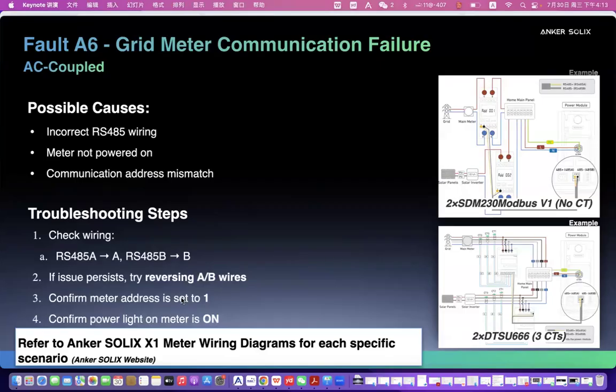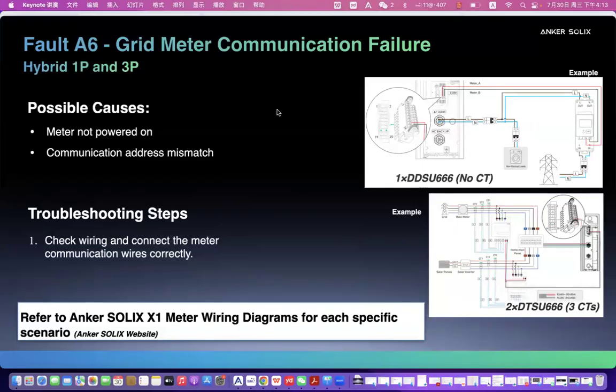And another thing to focus on is we also have this SDM230 Modbus V1 meter. This meter needs the address set, and other meters do not need the address set. So if the address is wrong, if the grid set address is wrong, it will also show this A6 error. Yeah, like this. And for the hybrid single phase and the hybrid three phase, I think I have already mentioned.